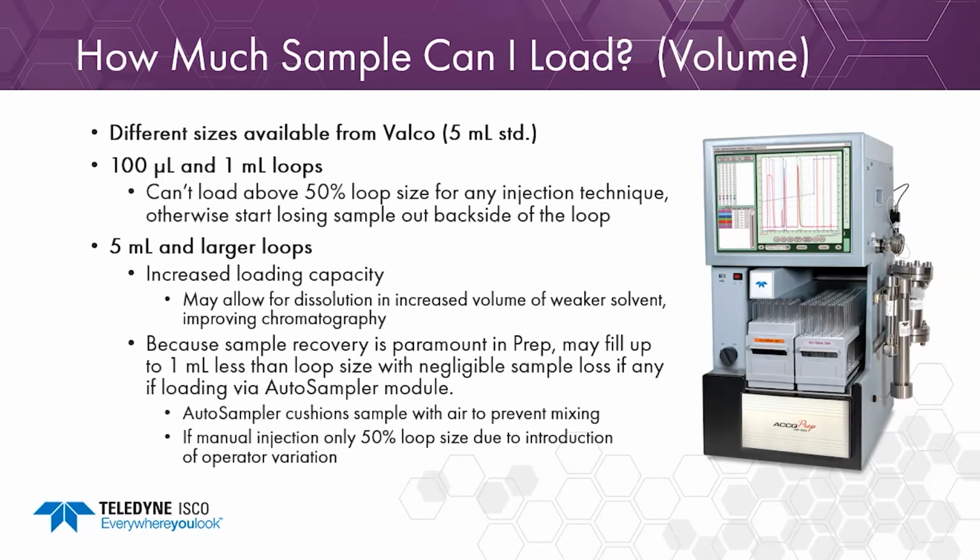If you're doing manual injection, like I said, only 50% of the loop size due to the introduction of operator variance, and you're not getting the air sample or air cushion between your sample and the mobile phase.